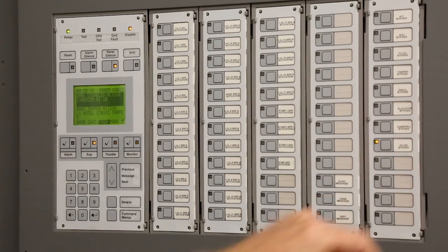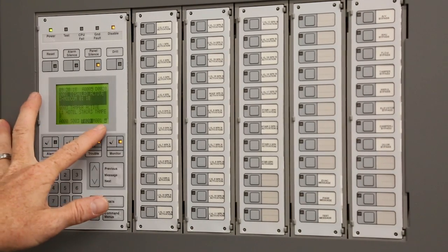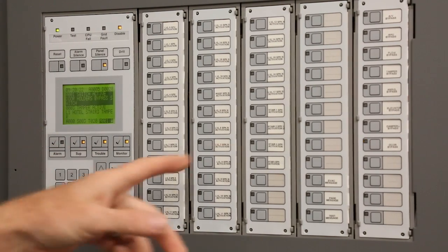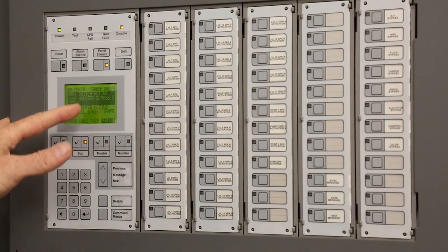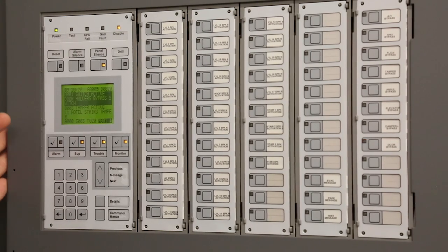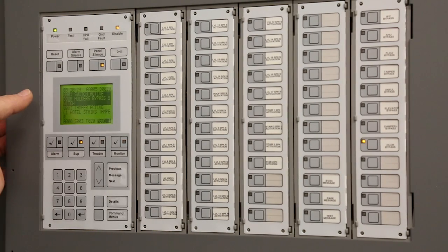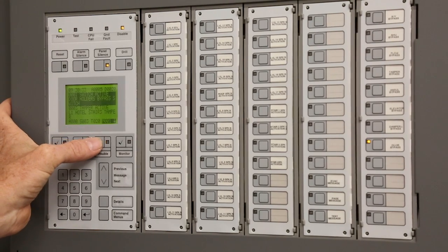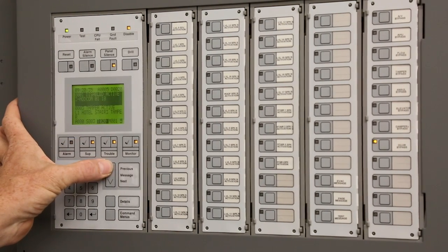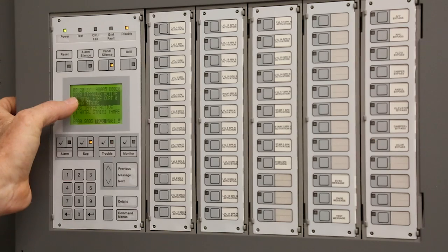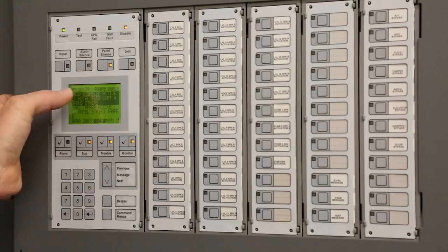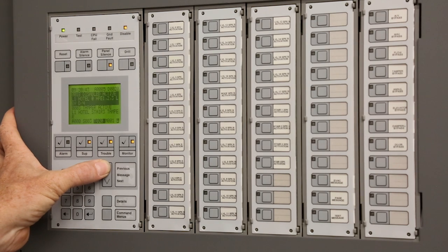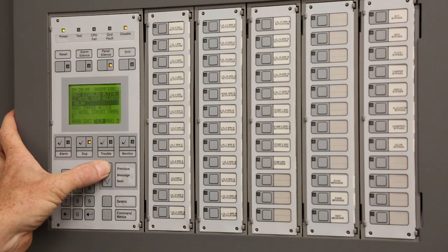For instance, like I said, right now we hit door bypass. If you notice, we got a monitor point active. If you want to know what it is, just hit monitor points, and it'll be more descriptive. It'll say right here the switch is active, door holder switch. So basically it's saying that the doors are bypassed. If you notice, the troubles went from 1 to 20 now, and we can scroll through them, go up or down arrow. Highest right there is 20, and they're all disable active.